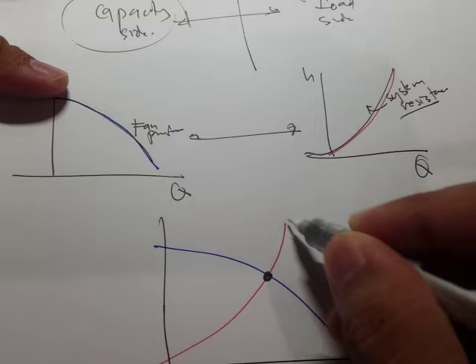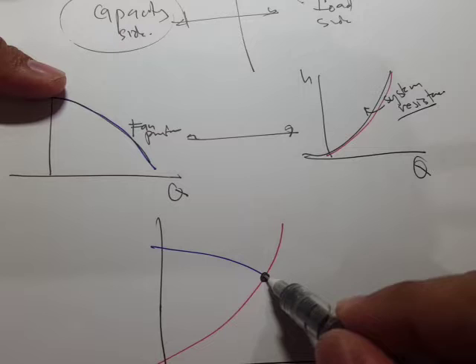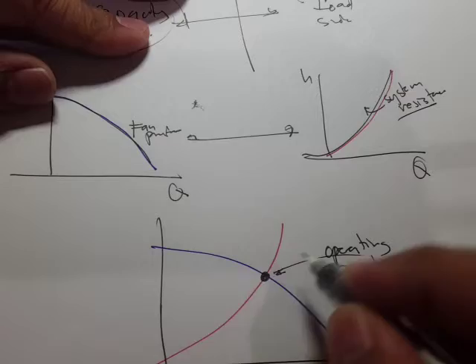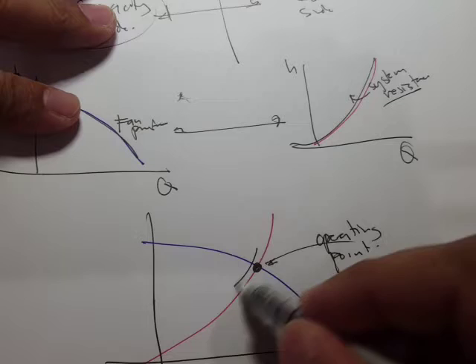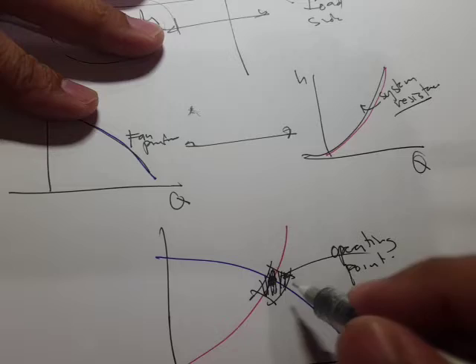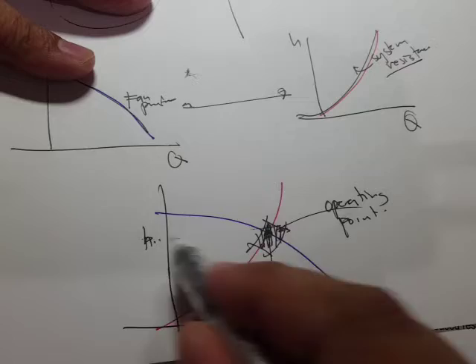The intersection point between the system resistance curve and the fan performance curve is called the operating point. Ideally, this is where we want to operate — the fan delivers the required flow rate at the required pressure. Since this is an estimate, there is a region around this point where operation is acceptable.